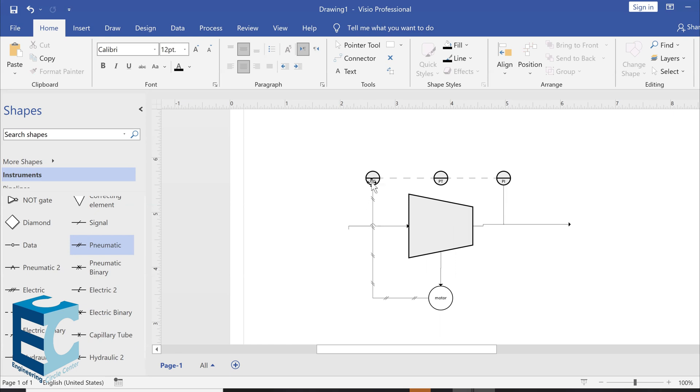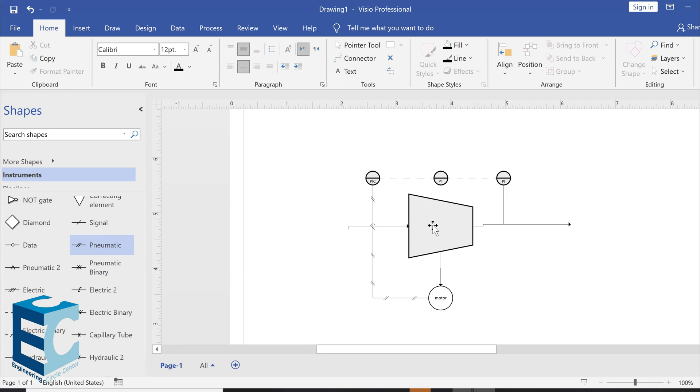Now, once the pressure indicator controller gets the signal, it will work, it will act on it, let's say. For example, if the pressure leaving the compressor is way higher than the design pressure, the pressure indicator controller will order the motor through this pneumatic signal to decrease its efficiency. And vice versa.